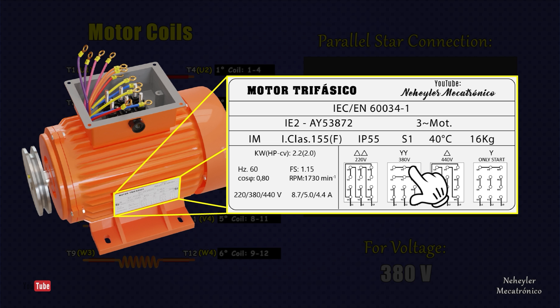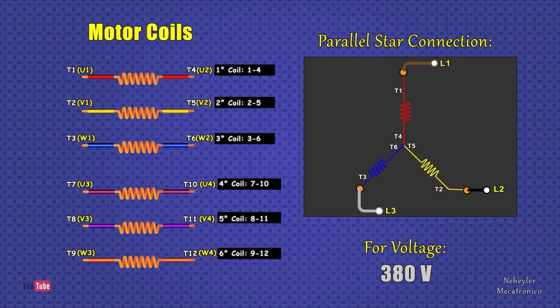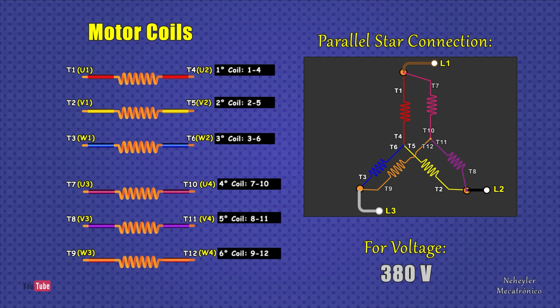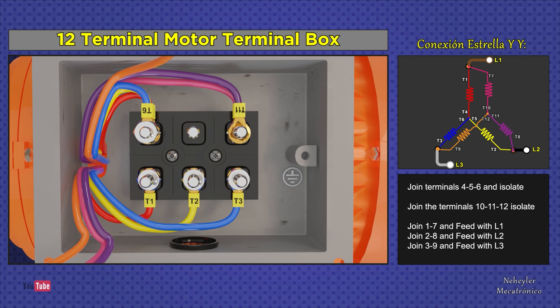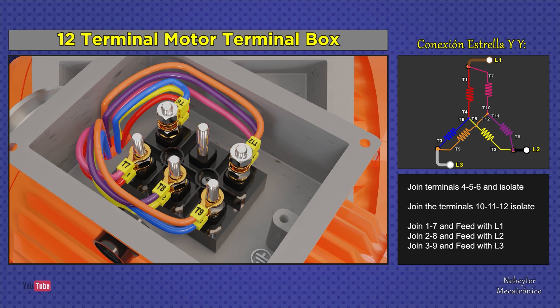For the parallel star or double Y configuration, a star is formed with the first three coils where terminals 4, 5, and 6 must be joined. Then another star is formed with the three remaining coils where terminals 10, 11, and 12 must be joined. These two stars are joined in parallel to feed the three lines. In the motor terminal box, terminals 4, 5, and 6 are joined to form the first star. In another terminal of the box, join terminals 10, 11, and 12. Finally, join terminals 1 and 7 to feed line 1, join 2 and 8 to feed line 2, and join 3 and 9 to feed line 3.